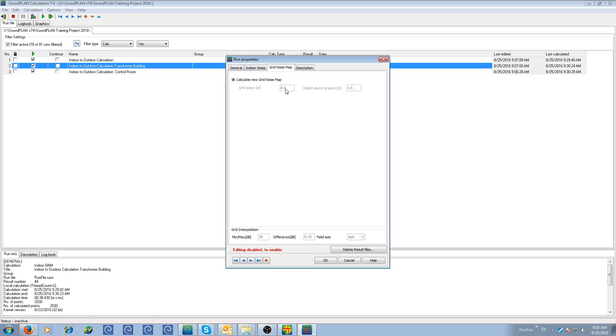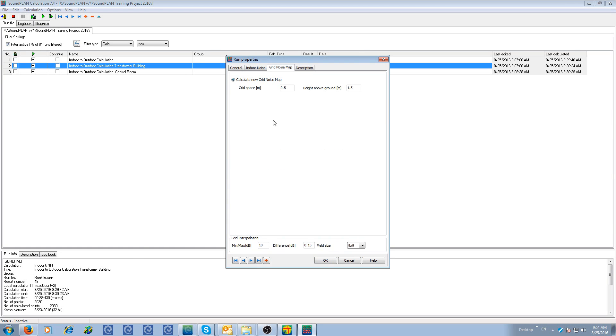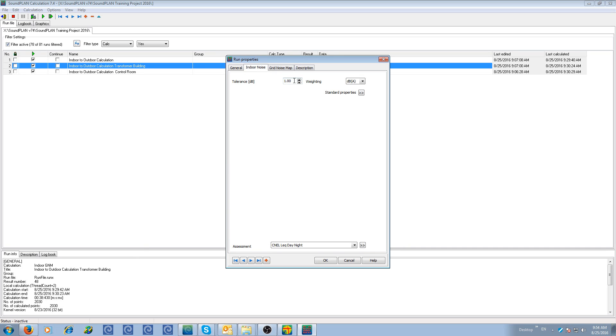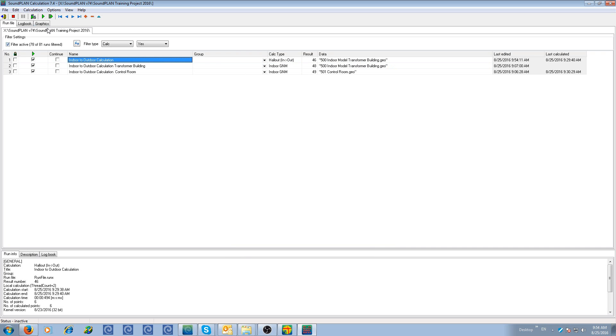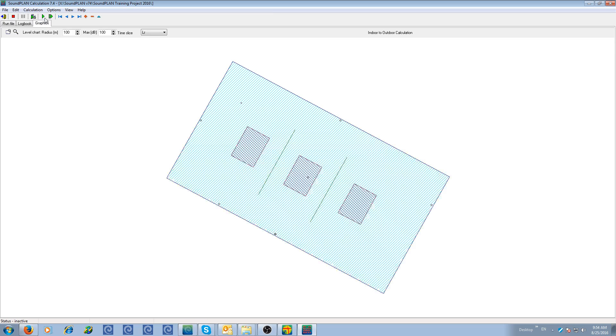The next calculation is a grid noise map. In this case, I set it up with a half meter grid, because it's a relatively small room. I just want to speed up the processing and I'll change the indoor parameter tolerance to two. And the third one is the same for the control room. So we can go to the graphics and run the model.